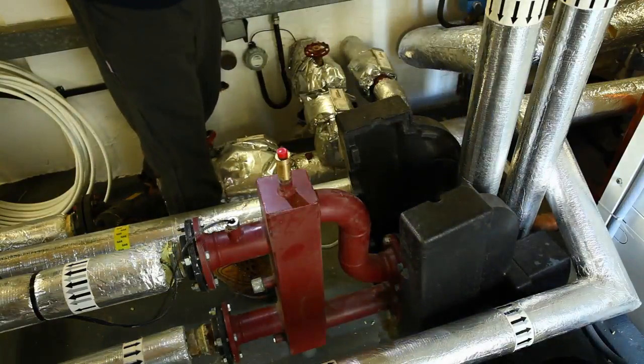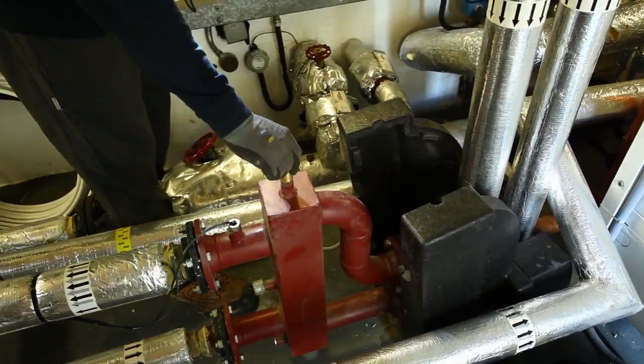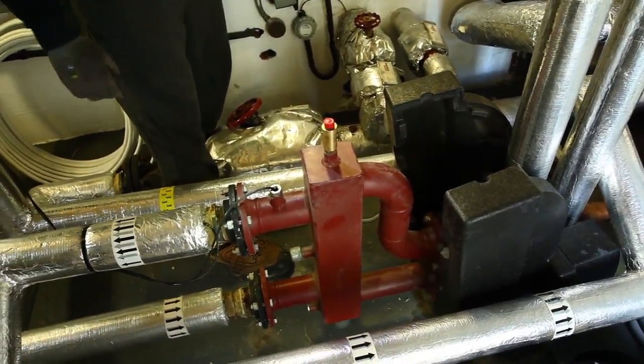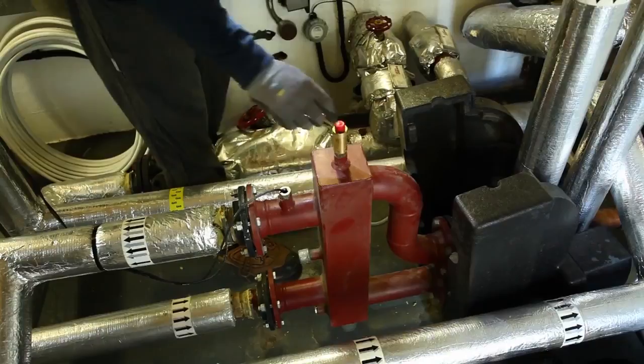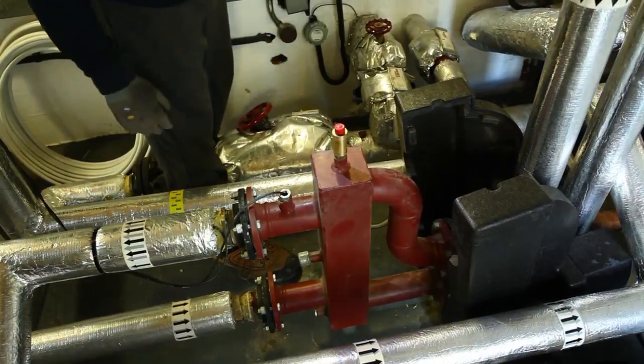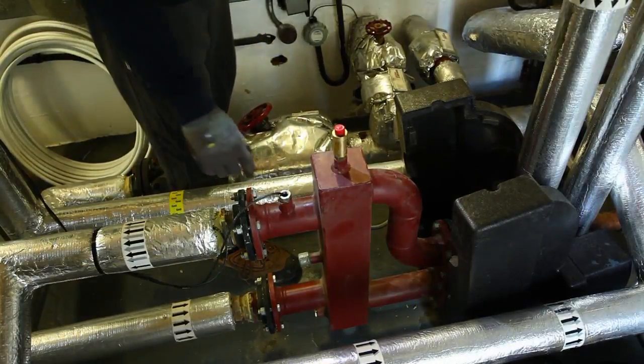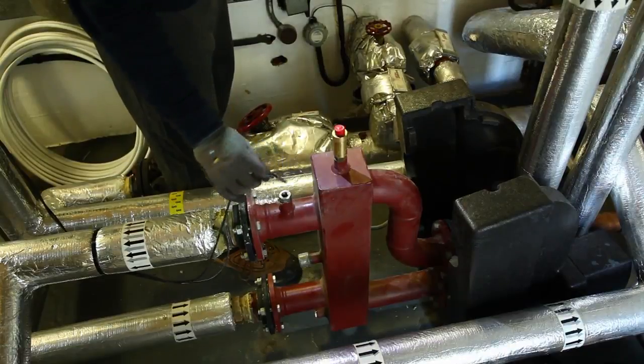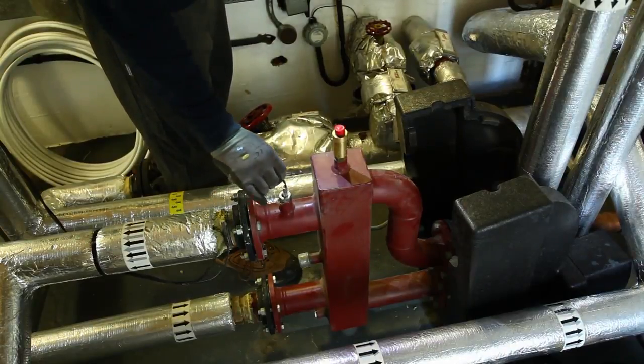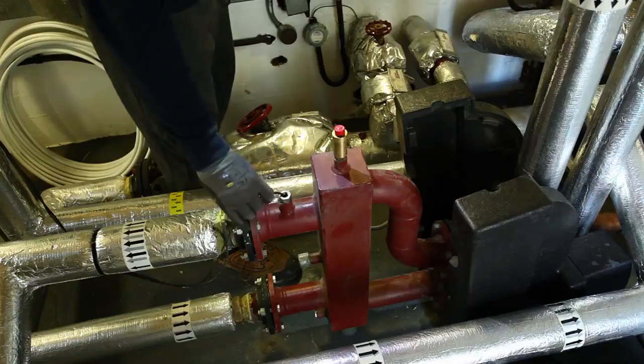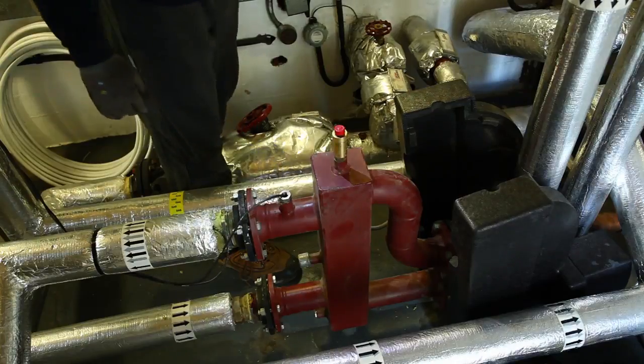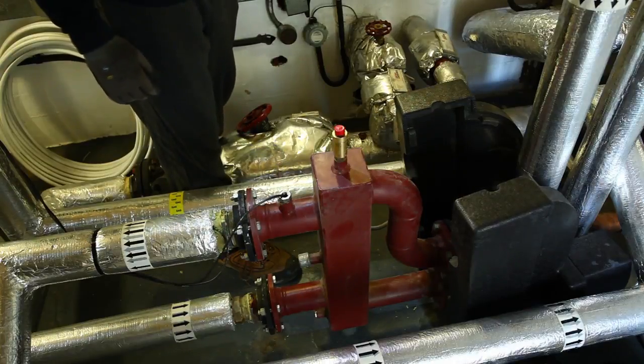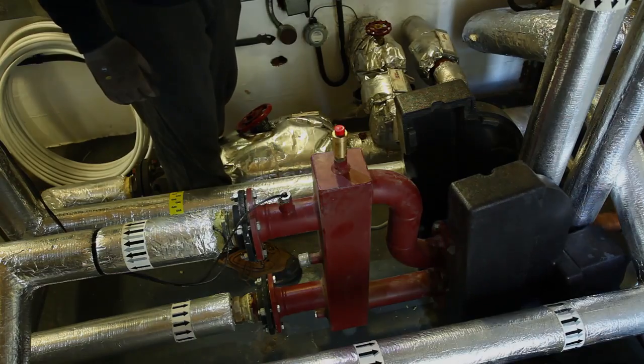On the header itself we have an automatic air vent. This bleeds the system of any air in the system to make sure that the system's always working at 100% capacity. This is our dry pocket sensor. This sensor here basically senses the flow temperature going out of the system, so the control module always knows the flow temperature going into the radiators and the heating circuit.